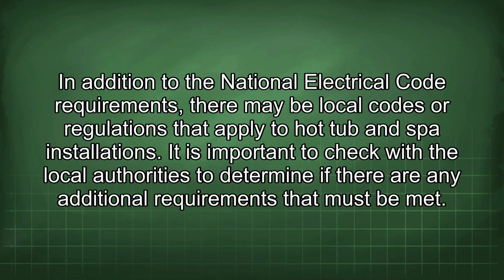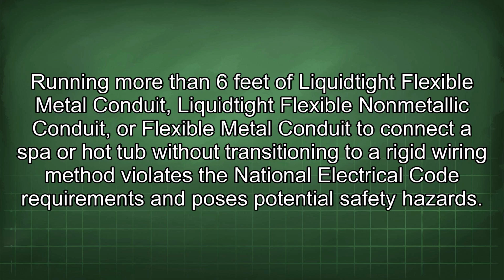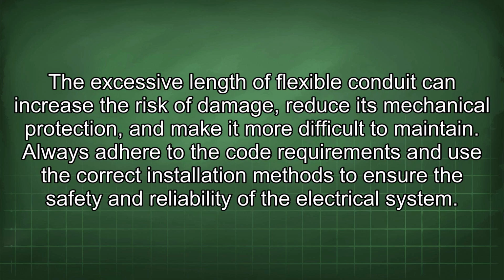In addition to the National Electrical Code requirements, there may be local codes or regulations that apply to hot tub and spa installations. It is important to check with the local authorities to determine if there are any additional requirements that must be met. Running more than 6 feet of liquid-tight flexible metal conduit, liquid-tight flexible non-metallic conduit, or flexible metal conduit to connect a spa or hot tub without transitioning to a rigid wiring method violates the National Electrical Code requirements and poses potential safety hazards. The excessive length of flexible conduit can increase the risk of damage, reduce its mechanical protection, and make it more difficult to maintain. Always adhere to the code requirements and use the correct installation methods to ensure the safety and reliability of the electrical system.